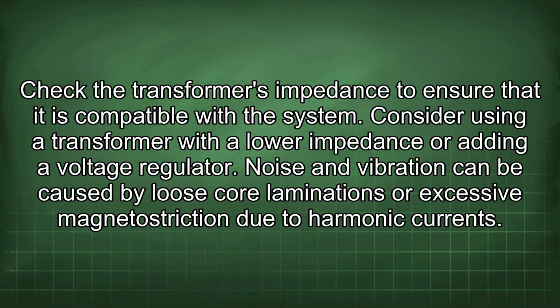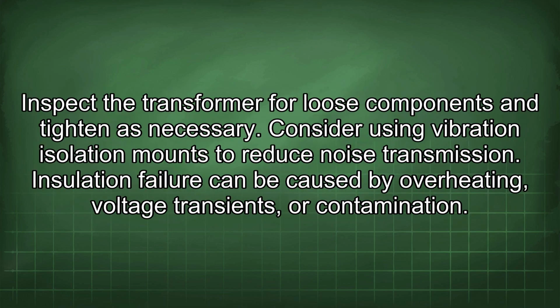Noise and vibration can be caused by loose core laminations or excessive magnetostriction due to harmonic currents. Inspect the transformer for loose components and tighten as necessary. Consider using vibration isolation mounts to reduce noise transmission.